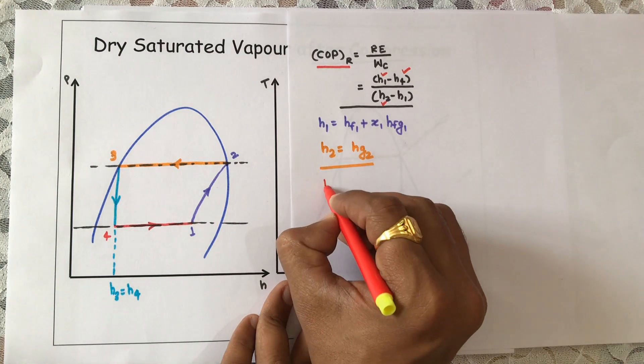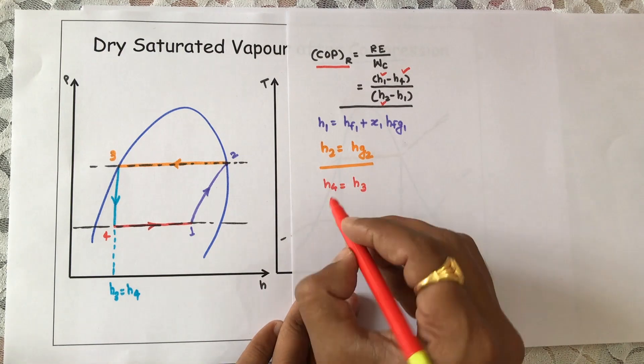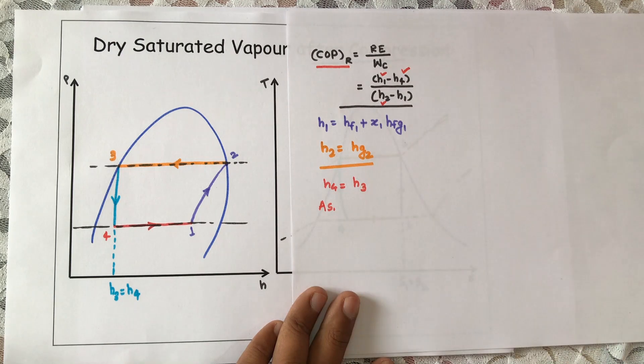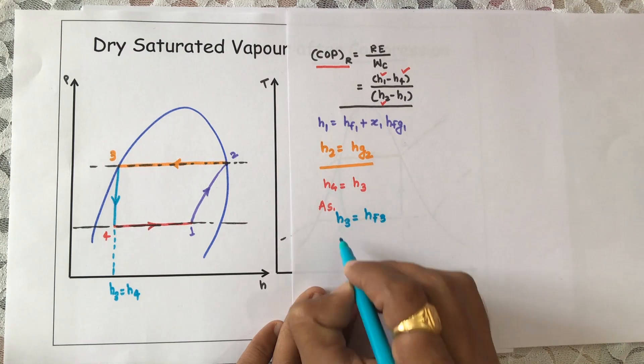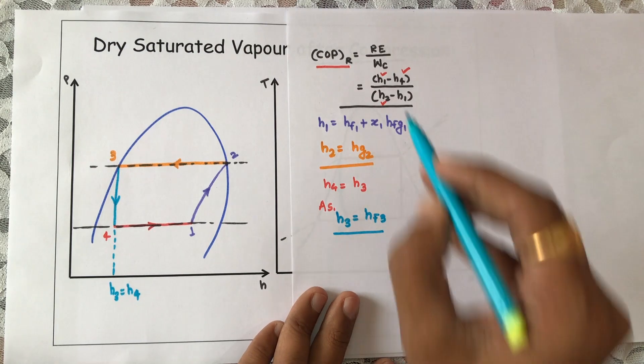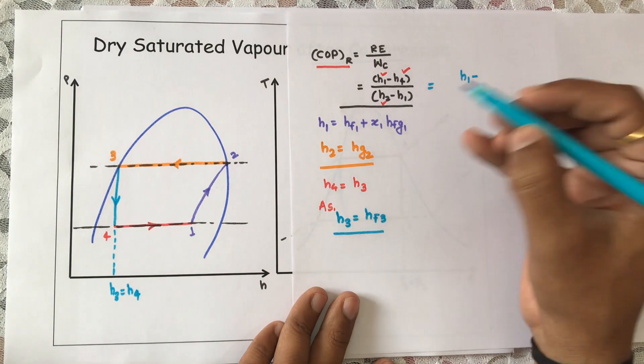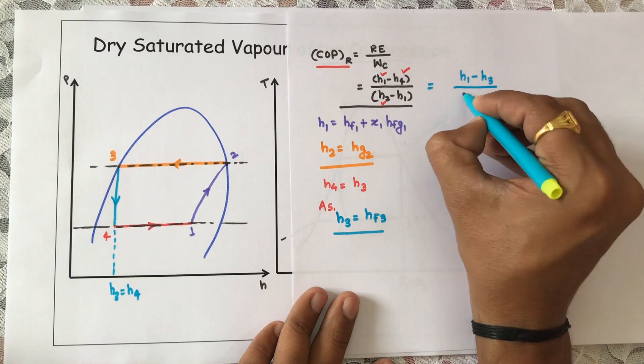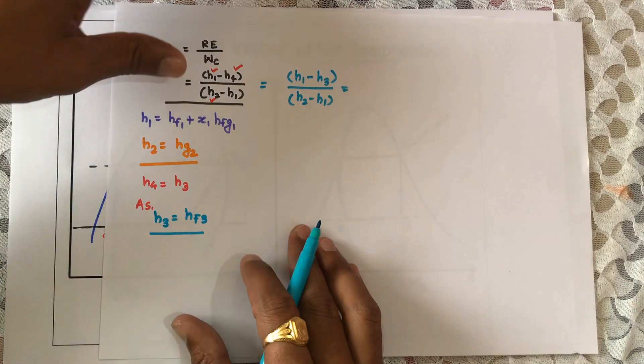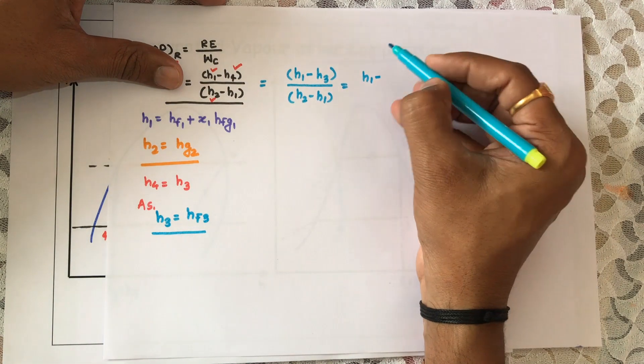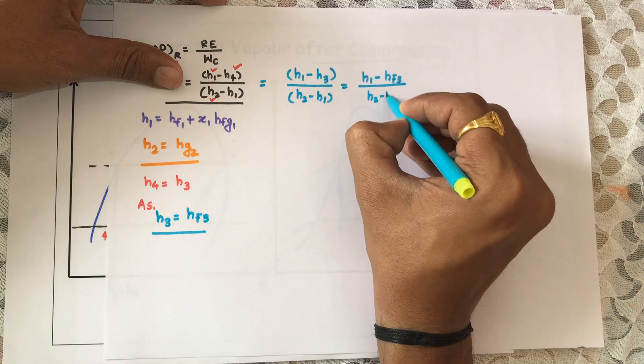For h4, since the process 3 to 4 is isenthalpic, h4 = h3. And h3 = hf3, since point 3 is on the saturated liquid line. Therefore, the COP equation becomes: COP = (h1 − hf3) / (h2 − h1).